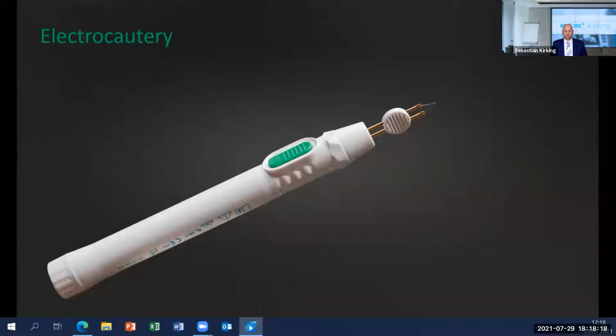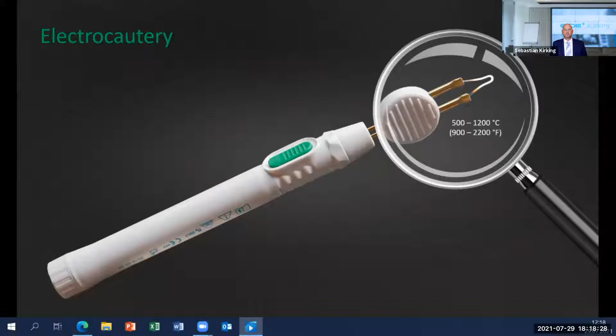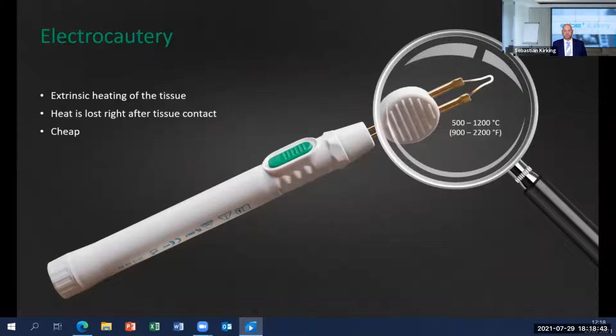Most often it is believed that the heat comes from the instrument and that electrosurgical instruments are nothing else than an electrocautery. Cauters are hot instruments, and its hot snare will cause the tissue effect. The problem of these instruments is that when the snare gets in contact with the tissue, the tissue cools the snare almost instantly, and the effect is therefore rather short and very weak. Let me explain in which way electrosurgical instruments work differently than such a cauter.